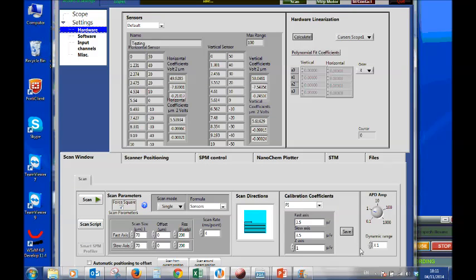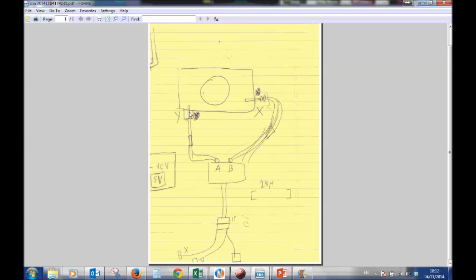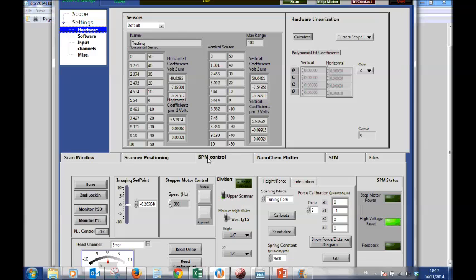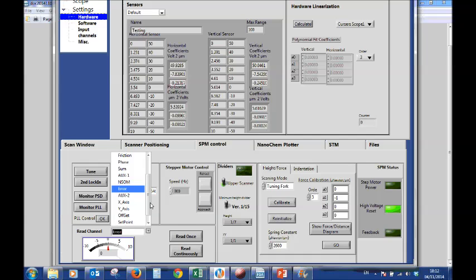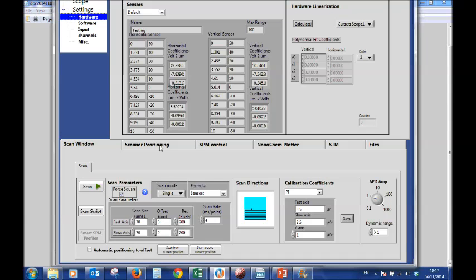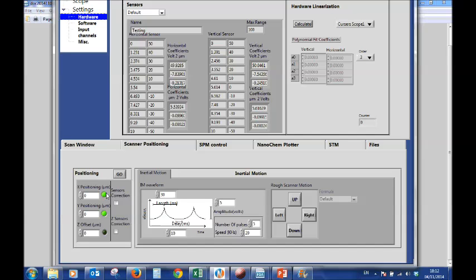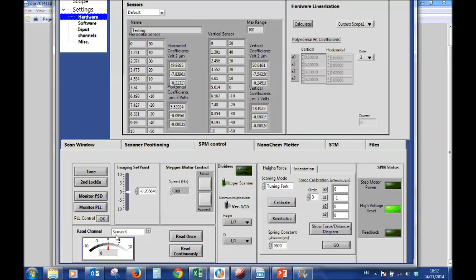To make sure that the hardware is calibrated also correct, that means that this sensor is pushed into the correct spot, and also this sensor is pushed into the correct spot. We have to check that in the software. So we go to this channel, and we're going to choose sensor X. Now, right now we are in the 0, 0 position. For example, here we can also make sure we can press go and go to the 0, 0 position. And then here, when we read this channel, we have to make sure that the sensor X will be at 5 volts, because 5 volts is our 0 position.